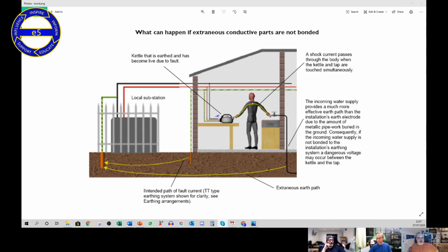The incoming water supply provides a much more effective path than the installation earth electrode, i.e. a very small CPC of 1.5 mil in a flex, rather than a big clunk of lead or copper, which is nicely buried in the ground. Consequently, if the incoming water supply is not bonded, then a dangerous voltage may occur.